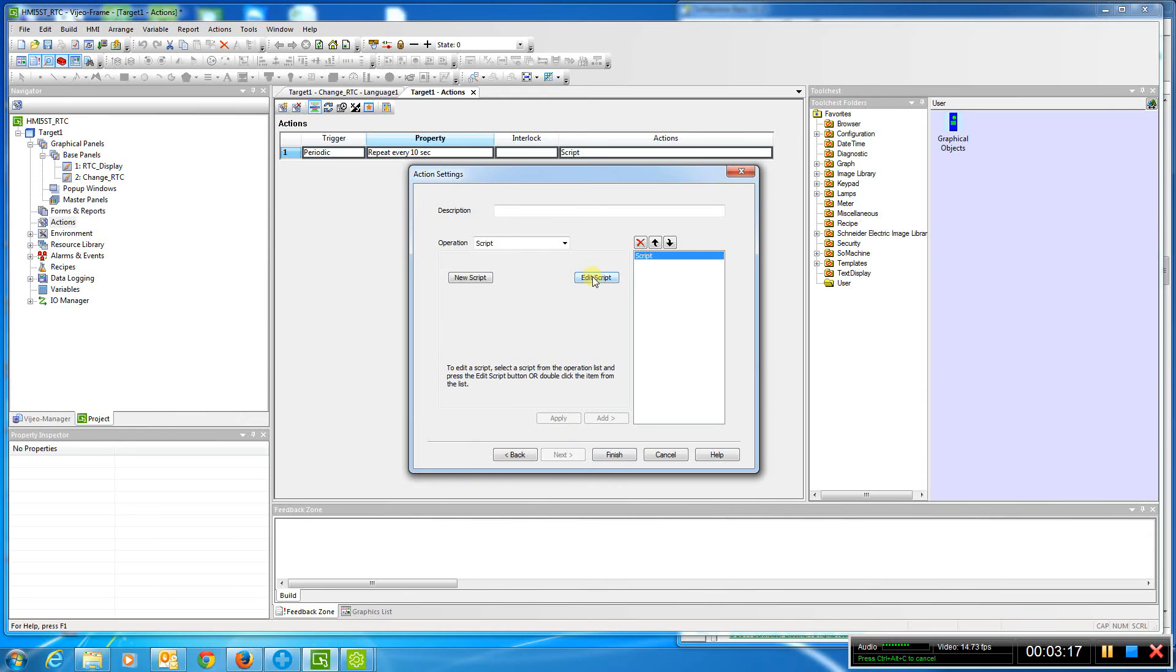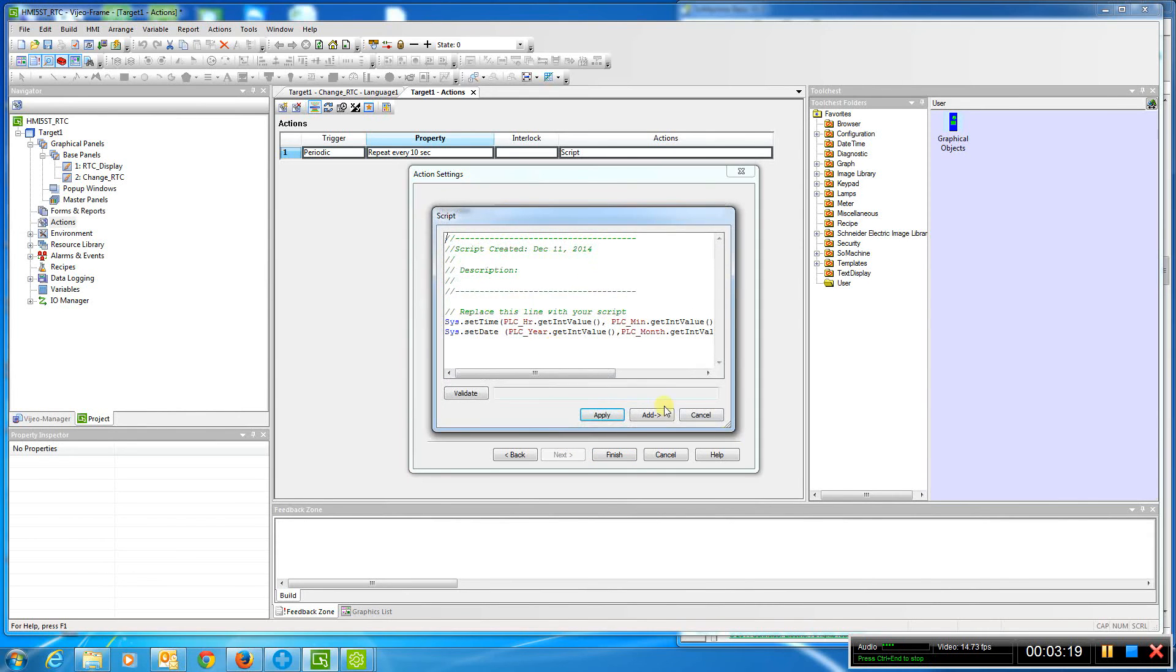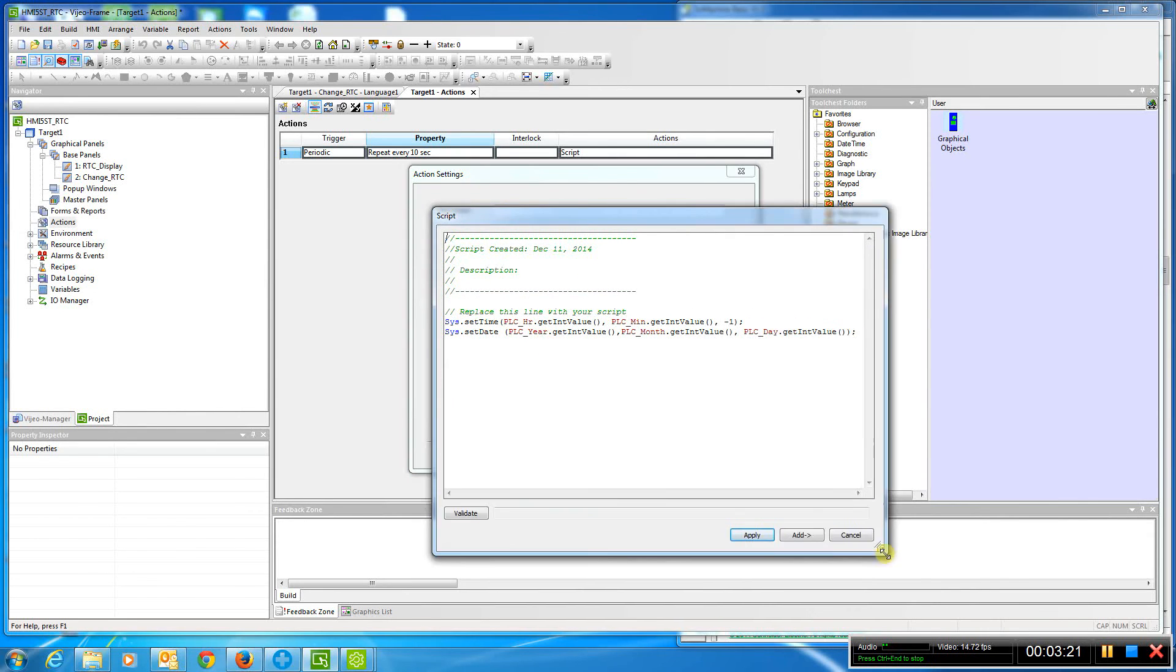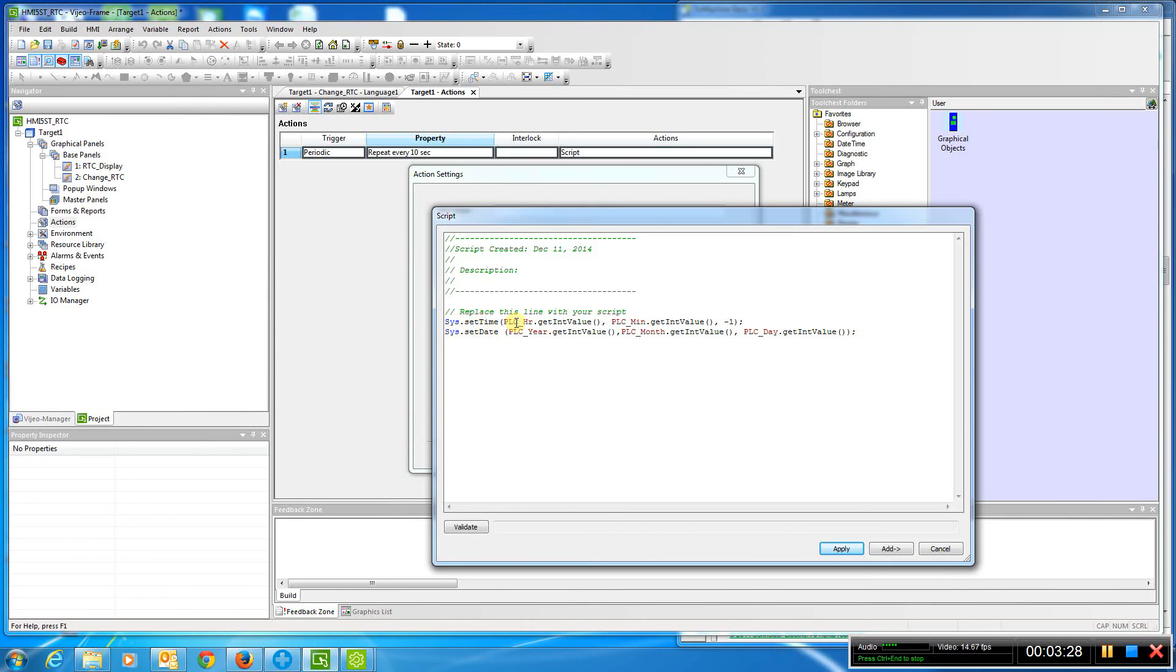In the script, if I go to edit the script, you can see the syntax isn't necessarily real friendly, but if you do a screenshot of this, you can see what it is. We're doing a SysSetTime and a SysSetDate, and we're taking the PLC hours and minutes and we're actually setting the system time using those variables here.